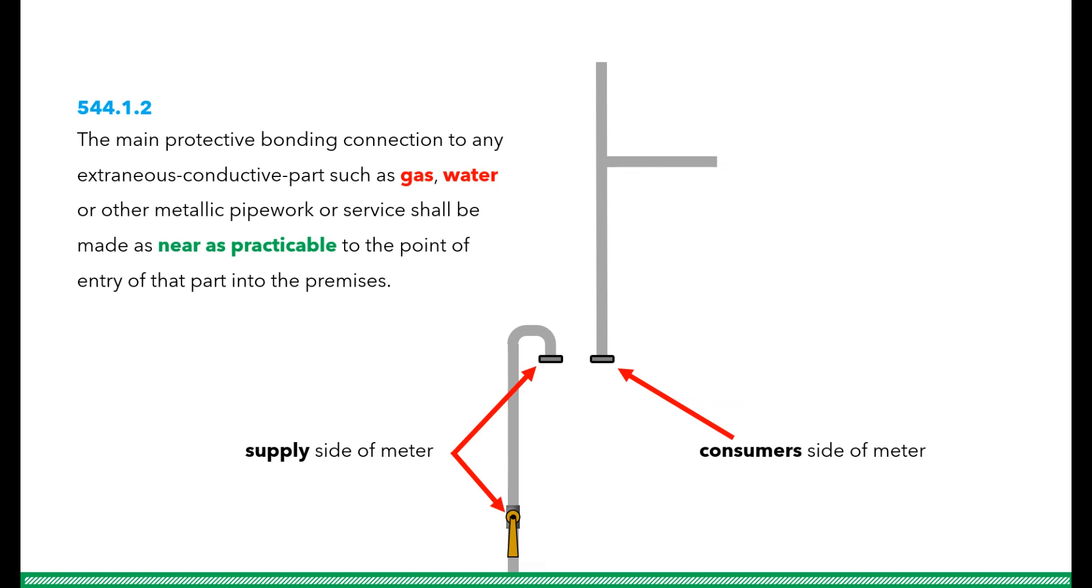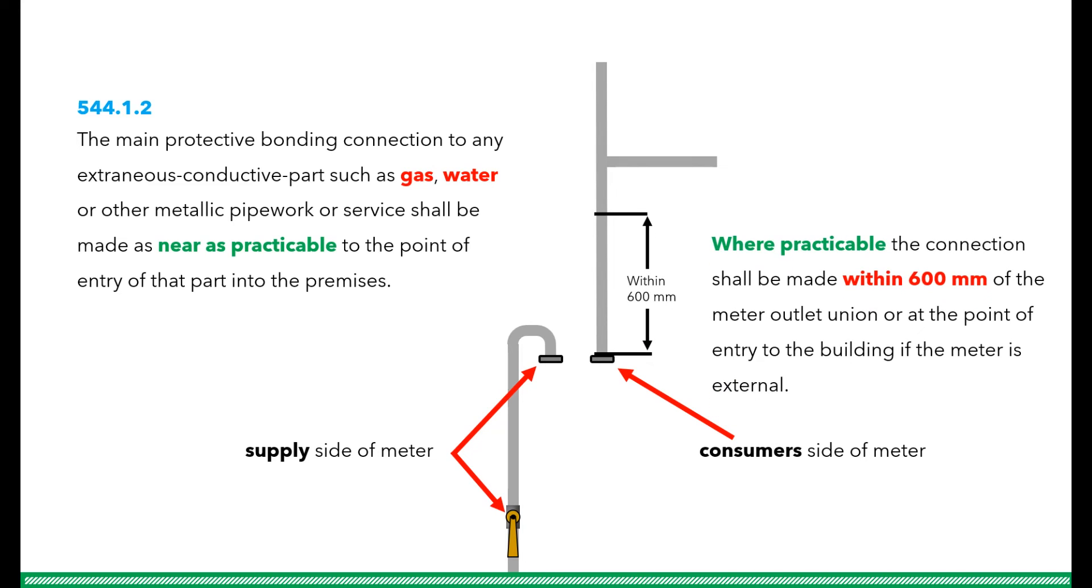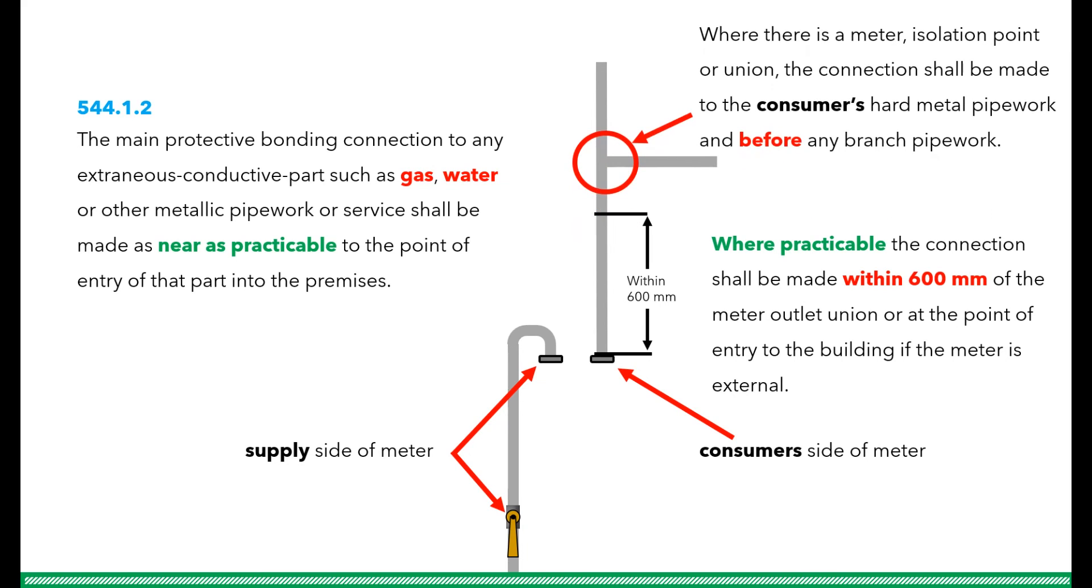This is why we bond the pipe work, as near as is reasonably practical at the point of entry. Where there is a gas meter, the connection should be made on the consumer side of the gas meter within 600mm, not on the supply side for the reasons we have just been discussing as that would be pointless. And just in case the gas fitters want to adjust the pipe work, we also try to ensure that it is before the first join, union or branch in the pipe work.